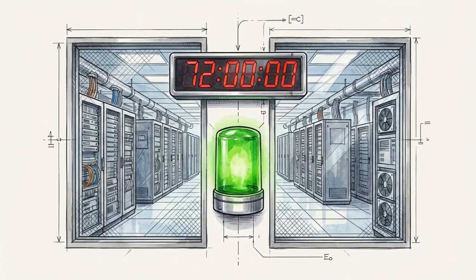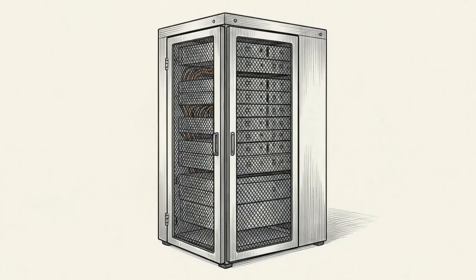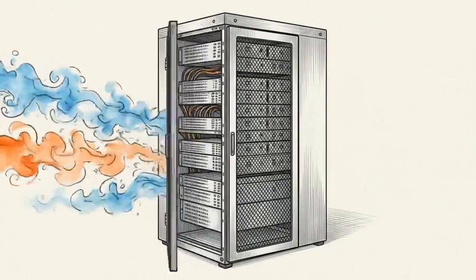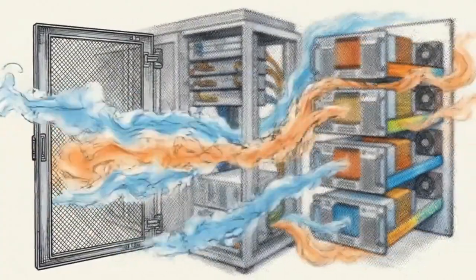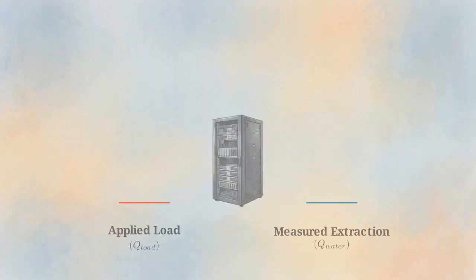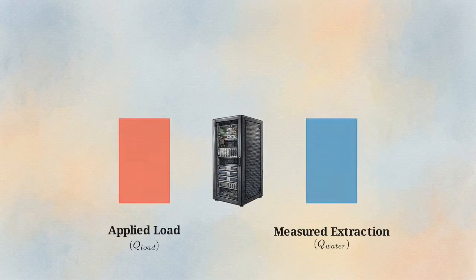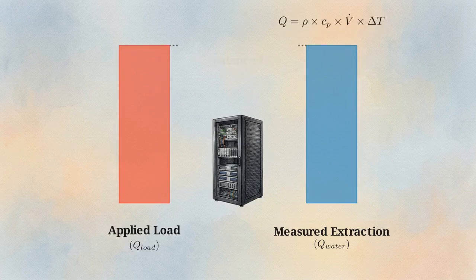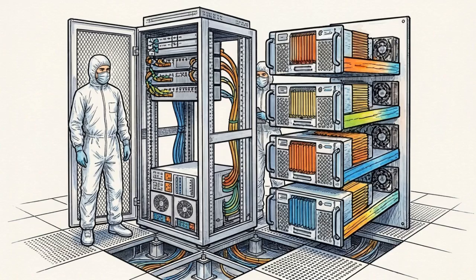During the continuous 24 to 72-hour heat soak, we conduct an aisle integrity stress test. By physically removing containment panels at full load, we force the floor cooling fans to dynamically reroute airflow in real time. Heat load testing mathematically verifies that the theoretical engineering capacity exactly matches actual spatial heat rejection, securing the physics before any IT equipment enters the space.